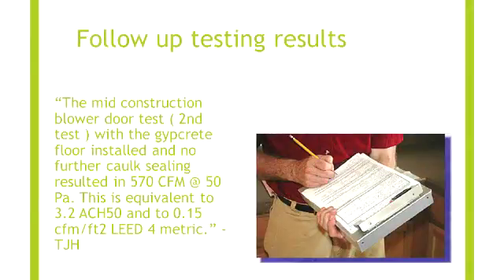And before we close out, right after we filmed this, we reached back out to our rater, Tom, and got some more details, as he promised, of the mid-construction review. And he said during the mid-construction blower door test, the second test, after the gypcrete floor was installed and there was no further caulking and sealing, they resulted in 570 CFM at 50 pascals, as you would normally do blower door testing. And according to Tom, this is equivalent to 3.2 air changes per hour at 50 pascals.